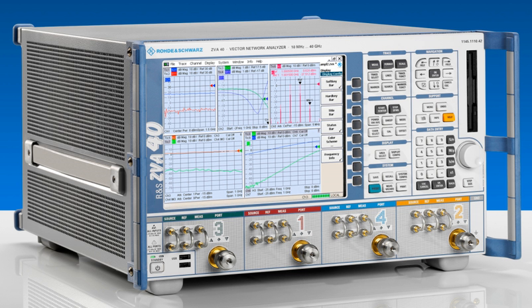When SW1 is set to position 2, the test signals are applied to P2, the reference is measured by RXREF2, reflections from P2 are coupled off by DC2 and measured by RXTEST2, and signals leaving P1 are coupled off by DC1 and measured by RXTEST1. This position is appropriate for measuring S22 and S12.